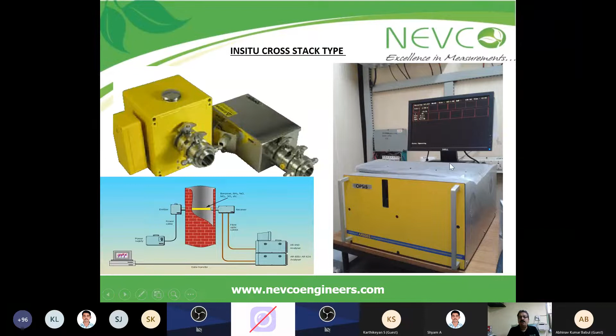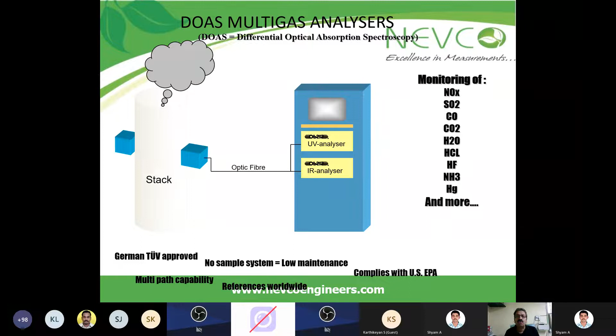This is another view of the differential optical absorption spectroscopy, again measuring through optic fiber cable. We have two analyzers: one UV, one IR. The same light can be differentiated into two instruments. SO2 and NOx are measured in the UV, while CO, CO2, and other particles are measured in the IR. This is TUV certified and USEPA approved. It also has multi-path and multi-stack capability—if you have 2-3 chimneys nearby, one analyzer can measure through light from all of them.